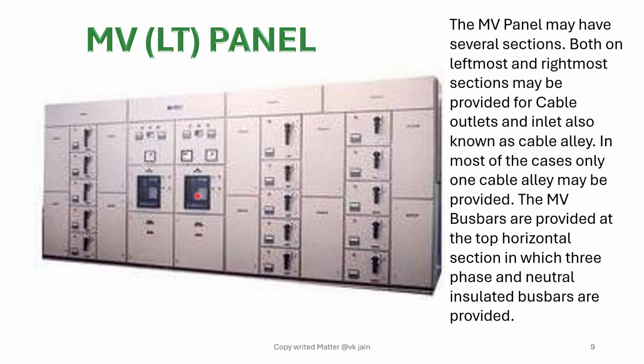The panel has two incoming air circuit breakers and one bus section which gets connected through this. These two are, one for normal supply, one for generator supply. Any one of these will get the power and the power bus is connected here. It will have three phase, one neutral and one earth, all duly insulated bus bar from here to here, so that it is easy to take connection to these MCCBs.